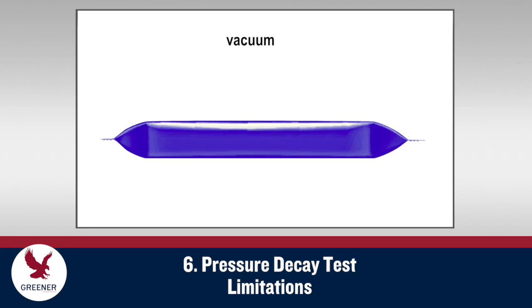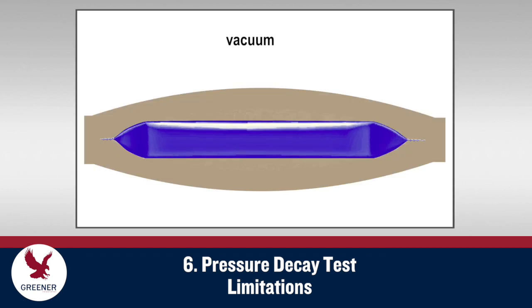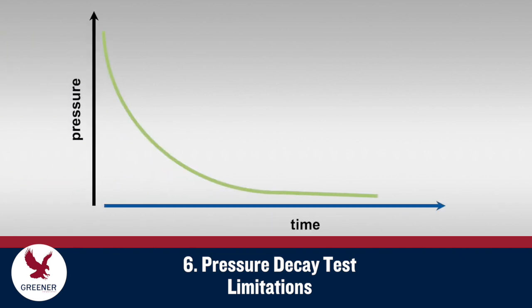With older pressure decay testing devices, the pressurized package will expand in volume. Excessive pressurization may result in seal creep or stretching and skew results, which limits the maximum seal test pressure, especially as package size increases. The newest devices resolve these issues by restraining the package in a flexible bladder that prevents the pressurized package from expanding, allowing much higher pressures to be used. Since the natural pressure decay rate decreases as pressure decreases, as illustrated on this graph, results from this test method are more precise for smaller leaks and lose accuracy as leak sizes increase.